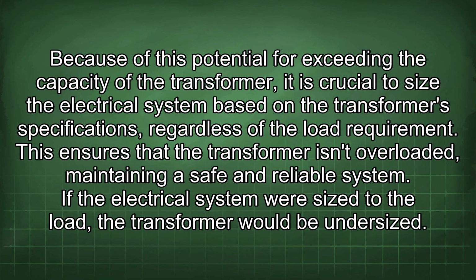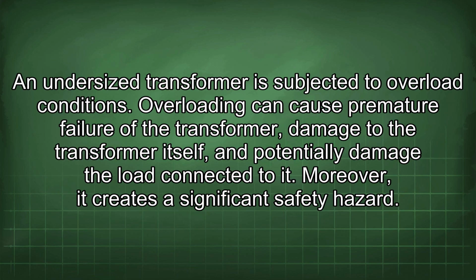If the electrical system was sized to the load, the transformer would be undersized. An undersized transformer is subjected to overload conditions. Overloading can cause premature failure of the transformer, damage to the transformer itself, and potentially damage the load connected to it. Moreover, it creates a significant safety hazard.